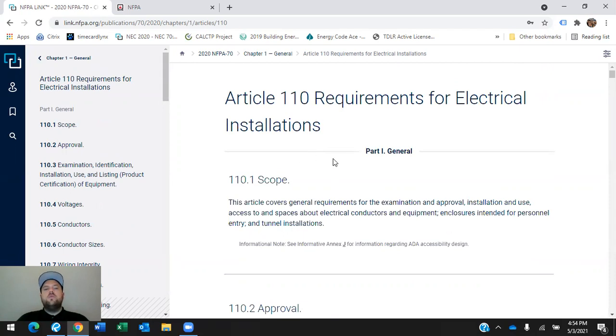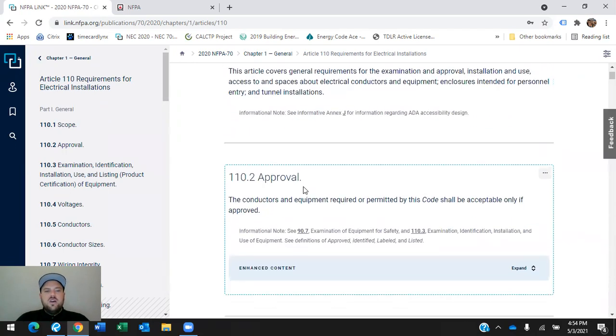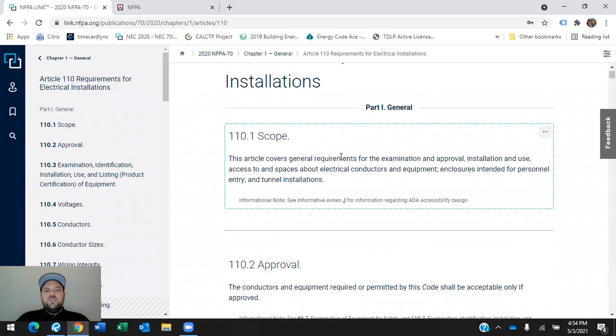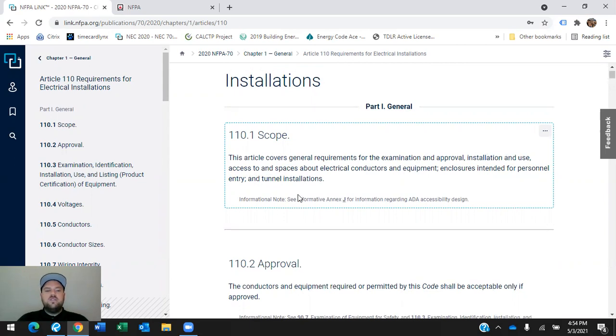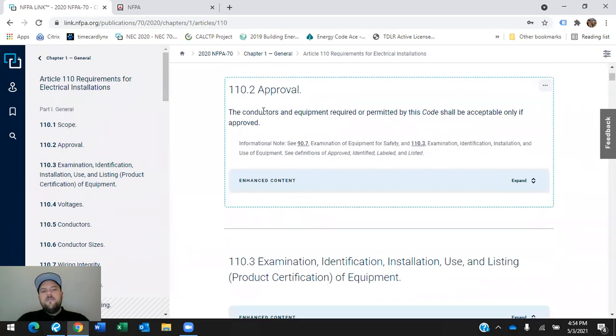Article 110, requirements for electrical installations. This article covers general requirements for the examination and approval, installation and use, access to, and spaces about electrical conductors and equipment, enclosures intended for personnel entry, and tunnel installations. Approval: the conductors and equipment required or permitted by this code shall be acceptable only if approved.